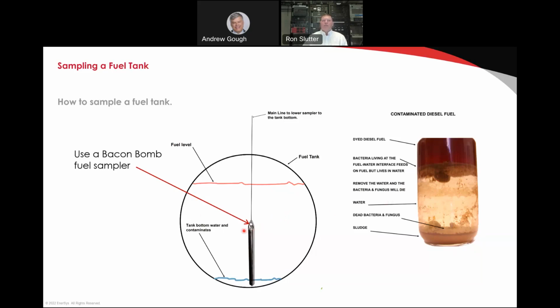If you do not specify the use of a specific tool, and I always laugh when I read this because I don't know why they call this tool a bacon bomb, but that's the right name. It's not a mistype. If you search for diesel bacon bomb, this is the tool you're going to find. This tool goes to the bottom of the tank, and you put a screw in the bottom to set where it will take the sample off the bottom of the tank. This is what you need to do. If you're not currently doing this to sample the fuel in your sub-base fuel tank of your generator, you're just waiting for disaster, because I guarantee you're going to learn a lot when you specify the use of this tool in your facility.